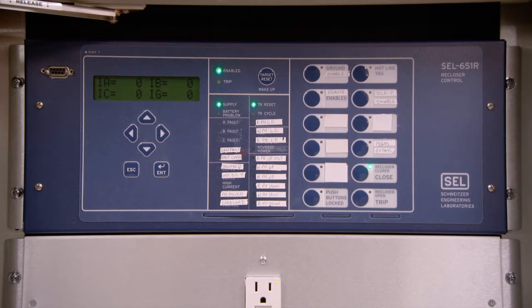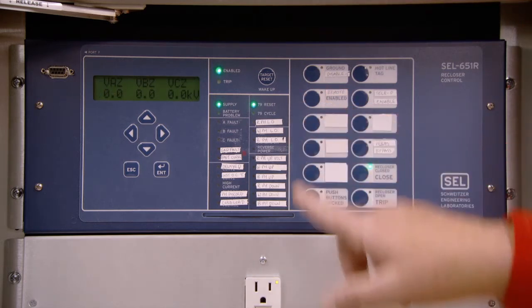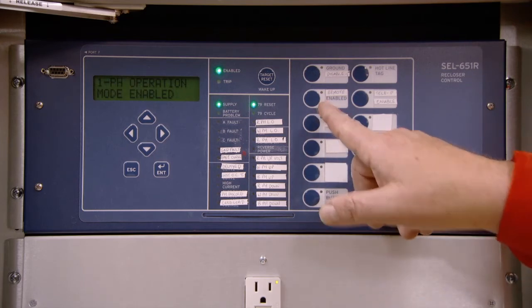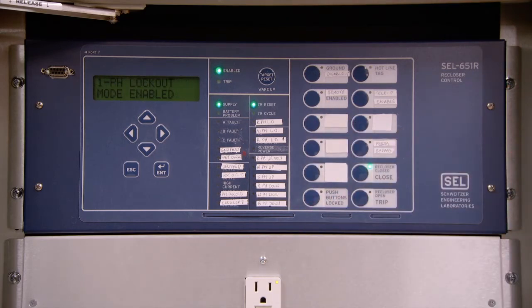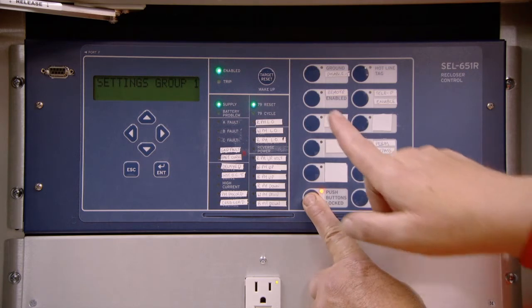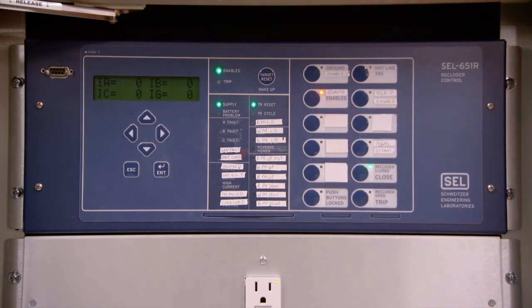To disable or enable remote communications is a 2-button operation. Begin by pushing and holding the push buttons locked button, followed by the remote enable button. The normal state of the unit, if it did have SCADA communications, would be an enabled state. To disable the remote communications, press the push button's locked button, followed by the remote enable button.